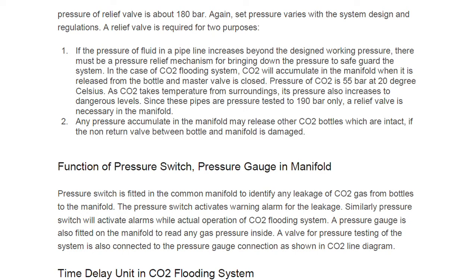In the case of the CO2 flooding system, CO2 will accumulate in the manifold when released from the bottle with the master valve closed. The pressure of CO2 is 55 bar at 20 degrees Celsius; as CO2 takes temperature from surroundings, its pressure increases to dangerous levels. Since the pipes are pressure tested at 190 bar only, a relief valve is necessary. There are two reasons for providing a relief valve: first, to protect the line from rupture due to high pressure; second, because accumulated pressure may release other intact CO2 bottles if the non-return valve between bottle and manifold is damaged.